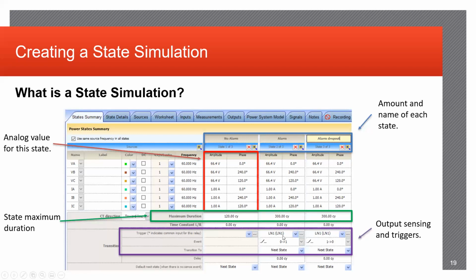During this section where there is a fault state is also where you want to put in your sensing contacts, because when you initiate a fault on a trip contact, you want the correct output contact to pick up when need be. Your test set will identify that and then return the nominal voltages and currents back to where they were.